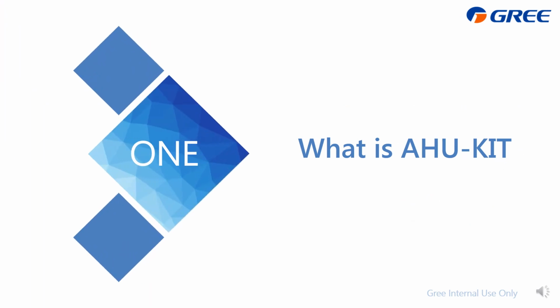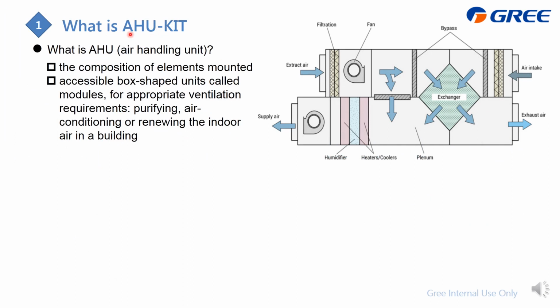First, what is AHU kit? Before that, let's talk about what is AHU, short for Air Handling Unit. This picture shows AHU is actually a combination of elements mounted for different functions. It can introduce fresh air and make heat exchange to improve energy efficiency. It can intake fresh air directly at 100%, or mix fresh air with indoor return air. Here is the cooler or heater and the humidifier, which is for air conditioning.